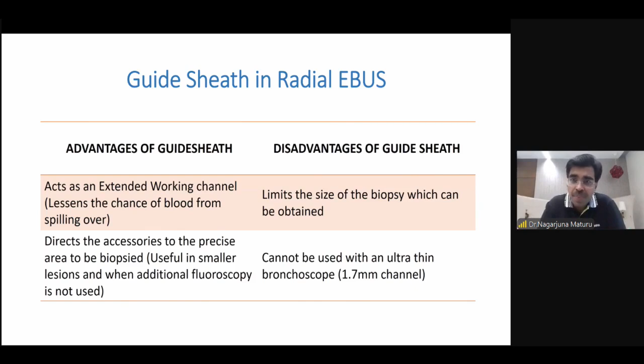Now we have to understand which scope is compatible with which radial EBUS and which guide sheath. So broadly speaking, you have four types of scopes: the conventional therapeutic scope, the thin scope, ultra thin scope, and the pediatric scope. So pediatric scope has a working channel of 1.2 mm, which means none of the radial EBUS probes would go. So with the ultra thin scope, which has the channel of 1.7, you can use radial EBUS, but without a guide sheath.